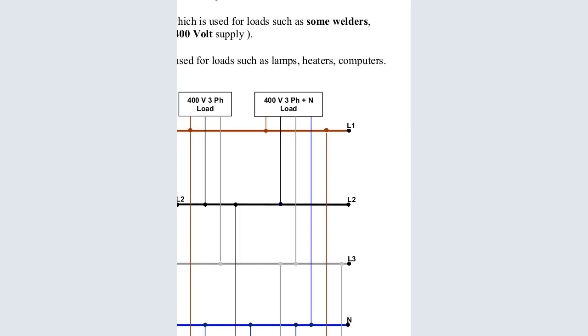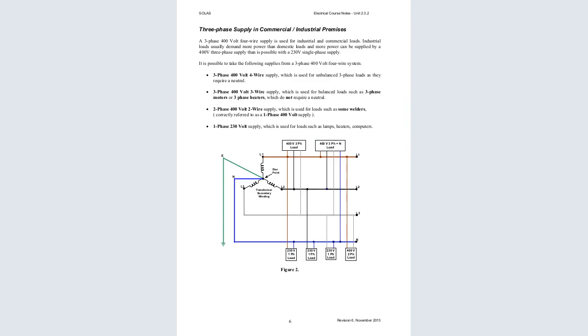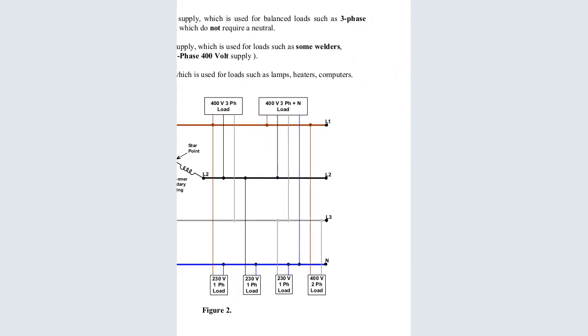When we say that it is 3-phase, it has to have 3 live wires. The first live wire is from line 1, that is in red. The second live wire is from line 2. You can see it being tapped here. I'm zooming so that you guys can see well. The second wire is from the black, that is line 2. The third live wire is from line 3. So it has the 3 lives. And then it is getting a neutral from here. Remember, our blue here was representing our neutral specifically for this diagram. So our neutral is tapped here. So this one is tapping 3 phases and a neutral.